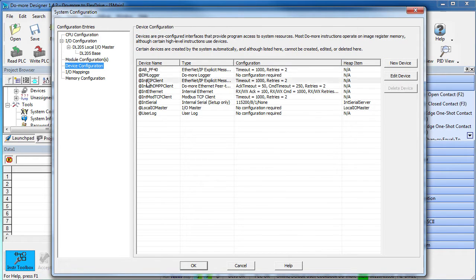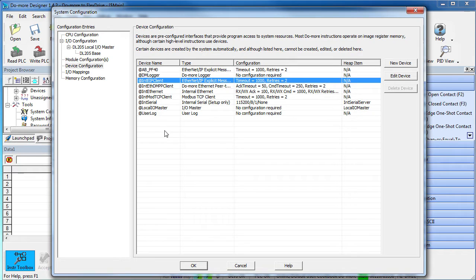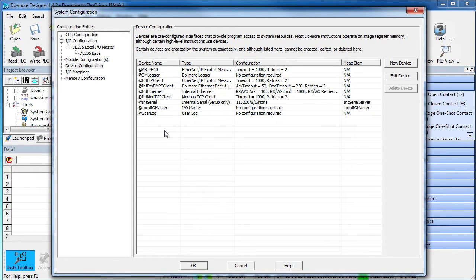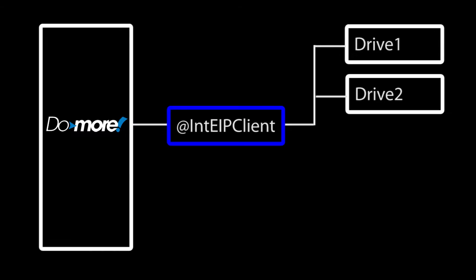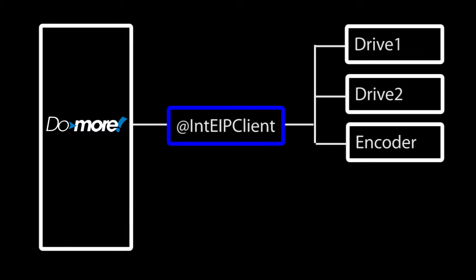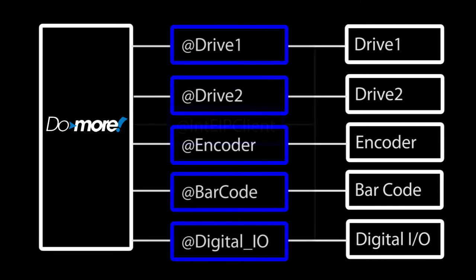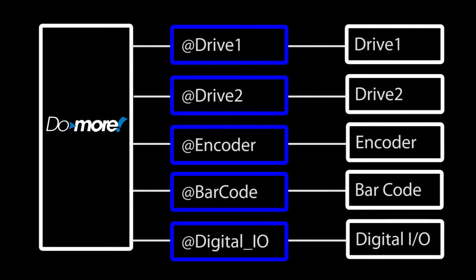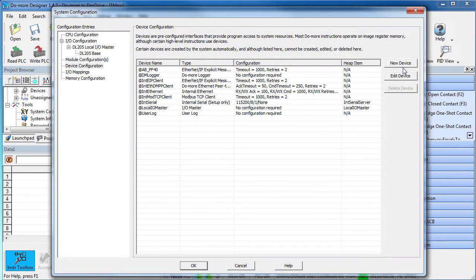Could we use this one generic Ethernet IP built-in device to talk to all of our Ethernet IP hardware? Sure. But it's much better to create a new DoMore device for each piece of Ethernet IP hardware because each one needs its own TCP IP connection. If you run all of those connections through one generic Ethernet IP device, it has to manage all of those, which slows things down. If each piece of Ethernet IP hardware has its own device, then things get real simple and much faster.